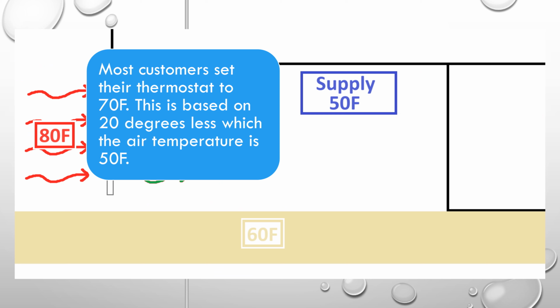All right, so I added the supply duct here. So right here is my supply duct. It's 50 degrees Fahrenheit. I kind of explained the last bit, typically where we set the thermostats to get 50-degree Fahrenheit. So our next step is going to be, what is the dew point? What is the dew point of this crawl space here?